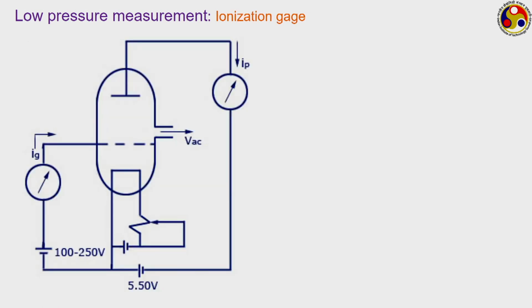And another device which can go to an even lower pressure level, up to 10 to the power minus 8 torr even, is called the ionization gauge. An ionization gauge is nothing but the conventional triode, where we have a grid, a plate, and a cathode. And we have a very low pressure gas inside this, that is, very few gas molecules. Now, this high temperature gas column, which may be somewhere in this particular zone, is subjected to a potential difference between the plate and the cathode, and when the pressure falls below a typical critical pressure level, then if we are able to impose a sufficient voltage, generally a value greater than a certain critical voltage, then it is able to lead to ionization.